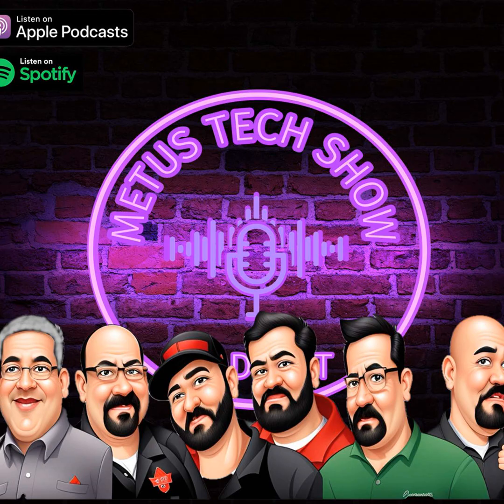All right, that brings us to number 3 on this list of things that could make or break your heat pump installation: failure to keep your system piping tight, clean, and dry. To me, the piping is the lifeline of that system. So right from the get-go, we've got to make sure that we're keeping all of that piping moisture-free and debris-free. We all know what moisture does to oil. It turns it acidic. Acid is bad inside of a compressor. It deteriorates the winding varnish, and you end up with a burnout.